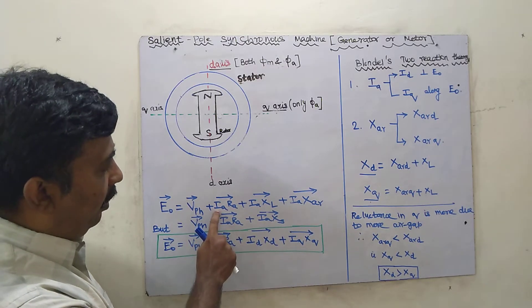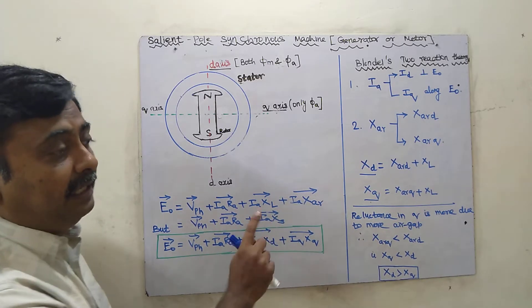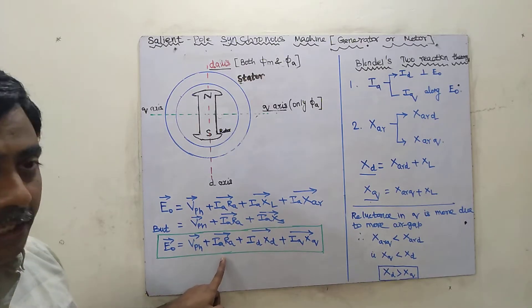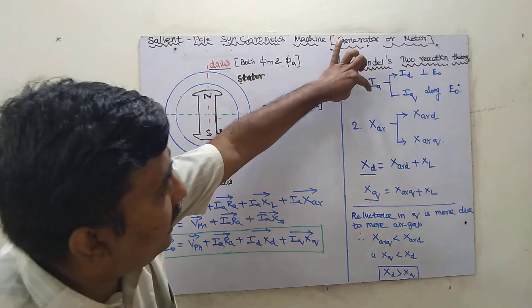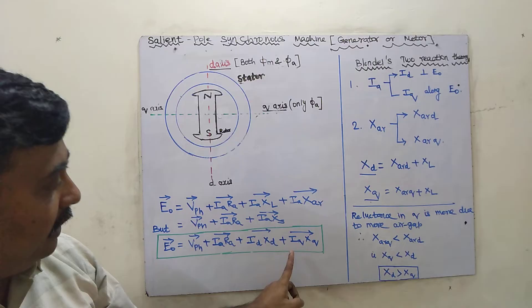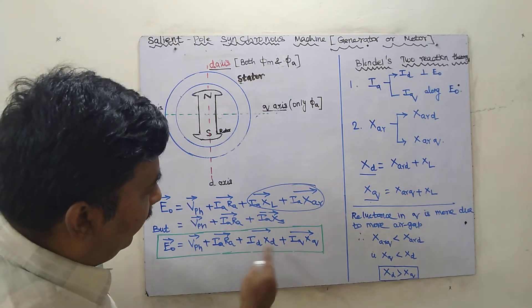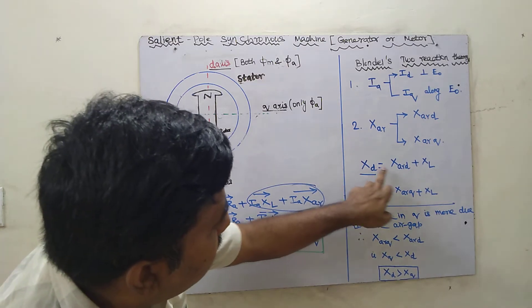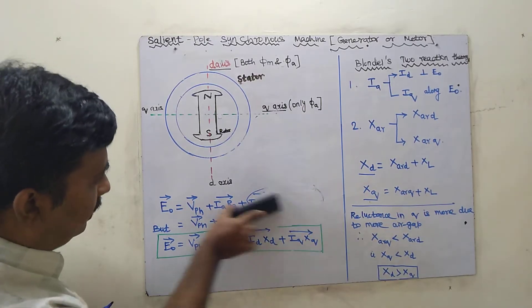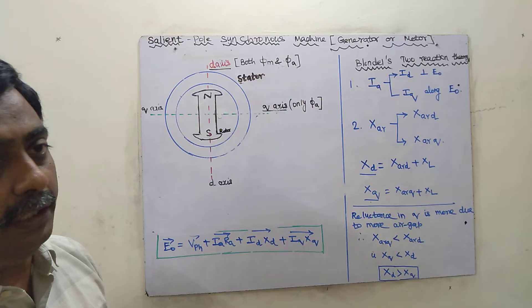The general formula for non-salient pole alternator is: E0 = V-phase + IA·RA + j·IA·XS. But this is not applicable for salient pole alternator. For salient pole, we divide the current into two parts — ID and IQ — and write: E0 = V-phase + IA·RA + j·ID·XD + j·IQ·XQ. XD consists of leakage reactance plus armature reaction reactance in the D-axis, and XQ similarly. From this equation, we find E0.